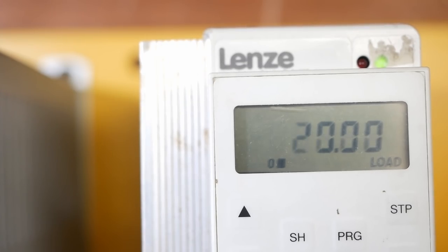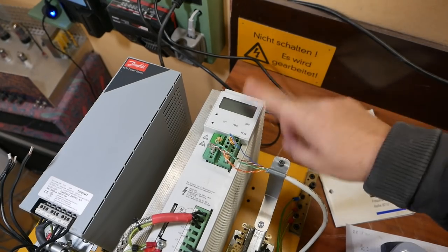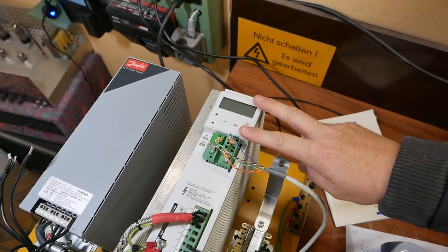So here it's running at its lowest speed at 20 hertz. If I crank it up to its higher speed which is 70 hertz, it accelerates cleanly and that works fine. But if I decelerate back down I get a couple of errors by the looks of it. So it looks like I can't dump the energy fast enough.